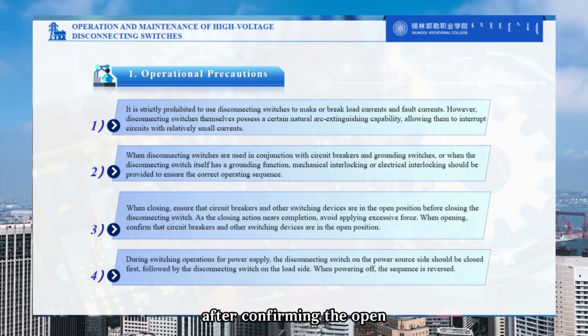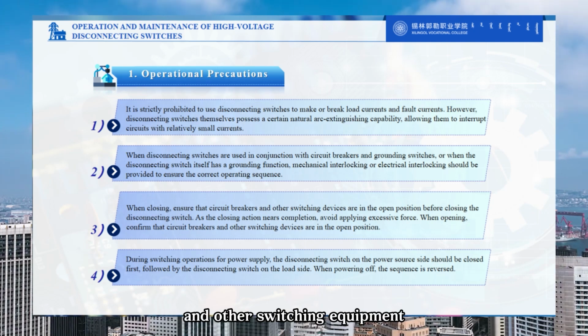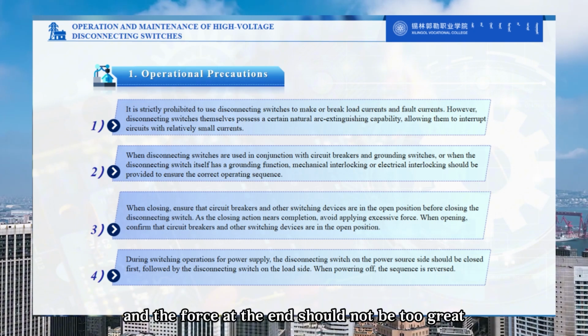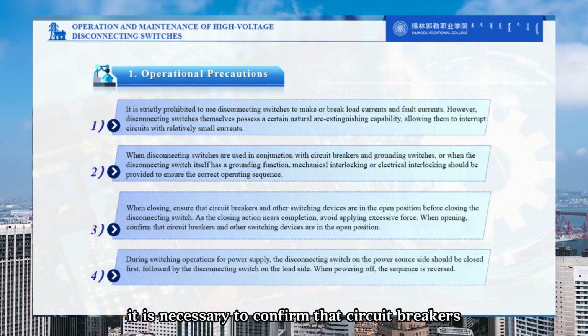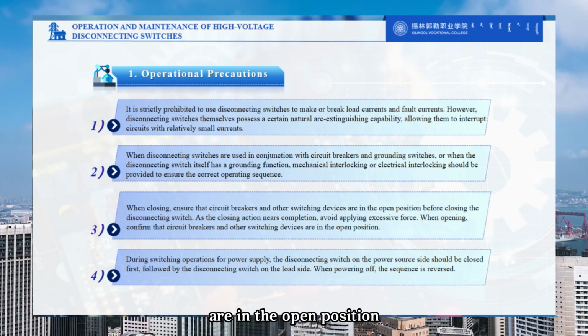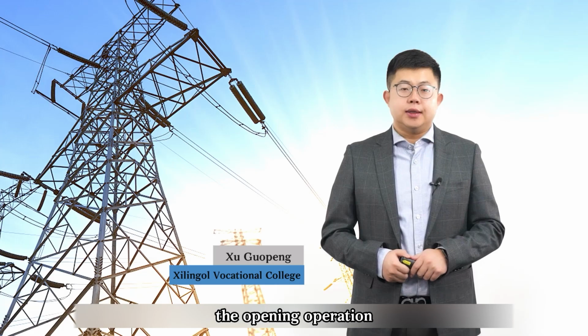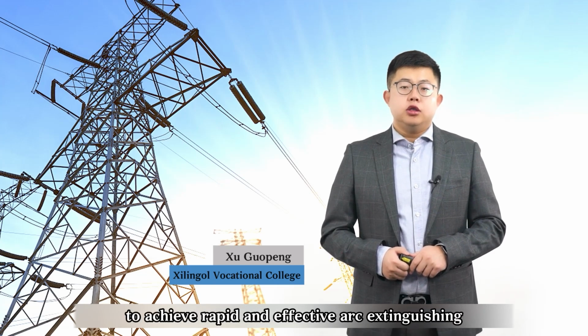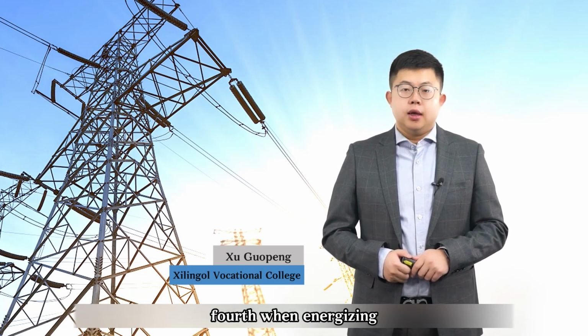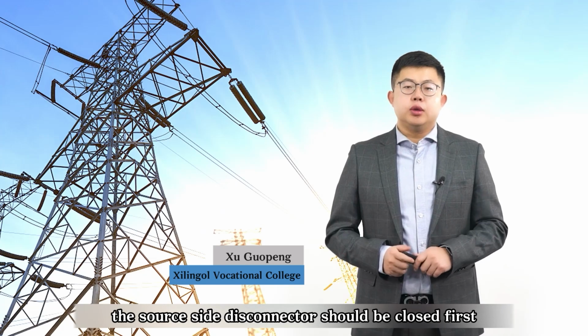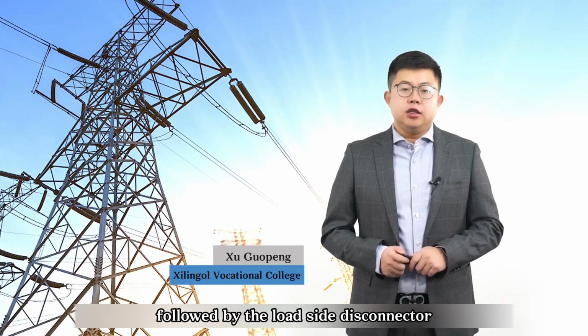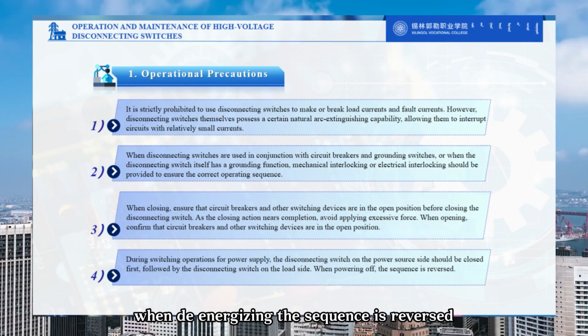Third, when closing, after confirming the open/close position of the circuit breaker and other switching equipment, the disconnector can then be closed. The closing action should be quick, and the force at the end should not be too great. When opening, it is necessary to confirm that circuit breakers and other switching equipment are in the open position. When used to break transformer no-load current and small load current, the opening operation should be performed quickly to achieve rapid and effective arc extinguishing. Fourth, when energizing, the source side disconnector should be closed first, followed by the load side disconnector. When de-energizing, the sequence is reversed.